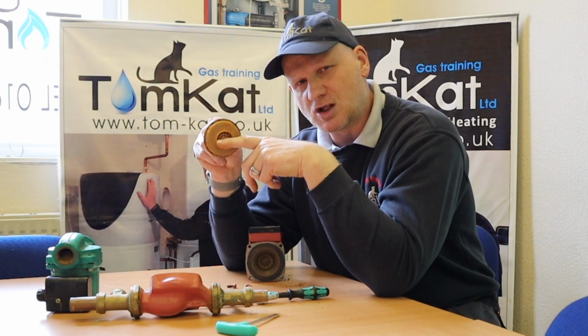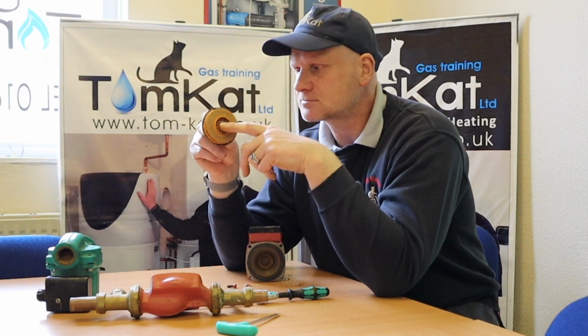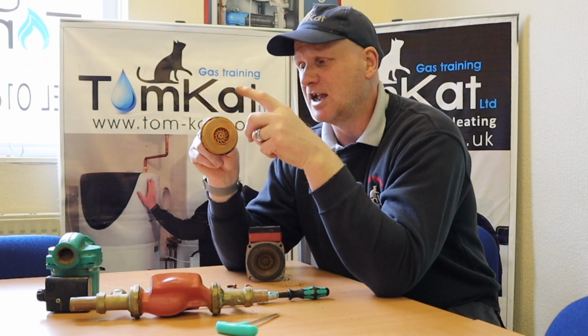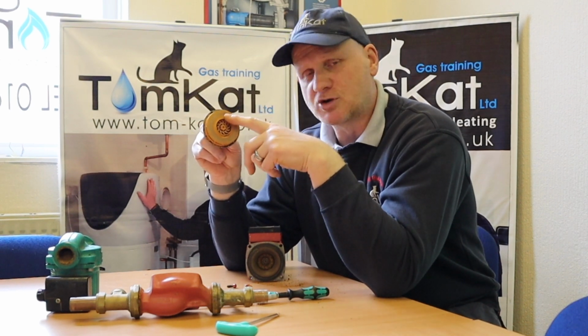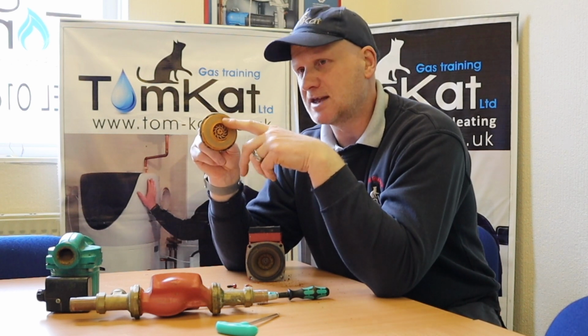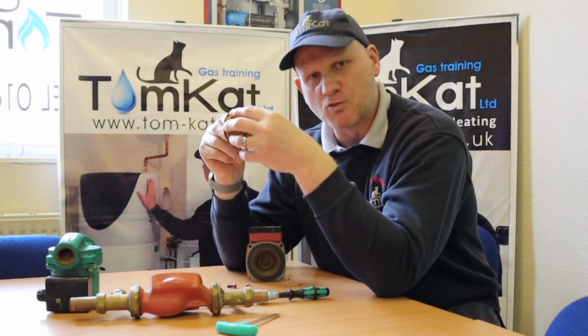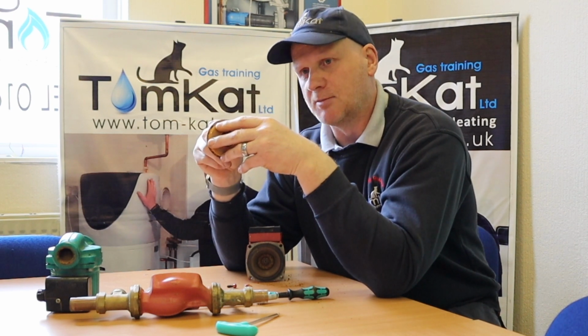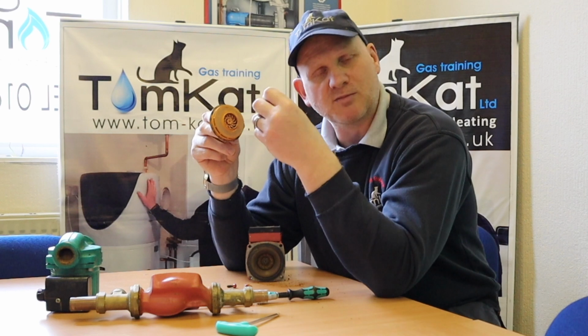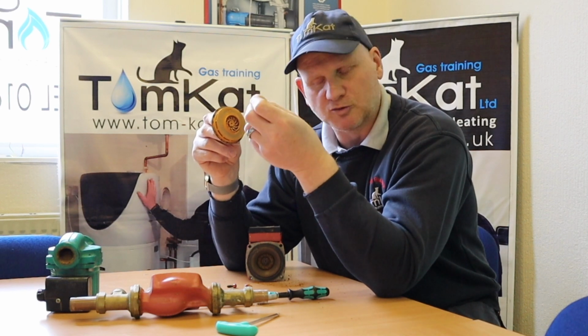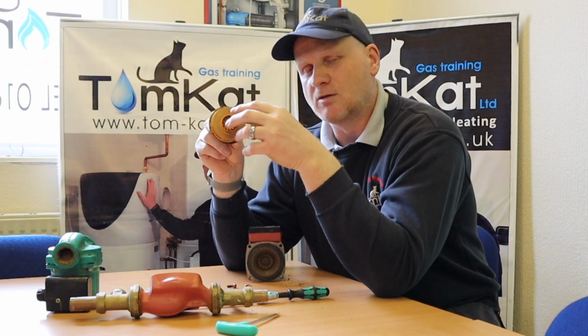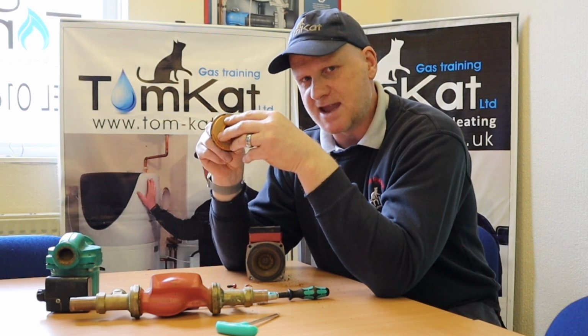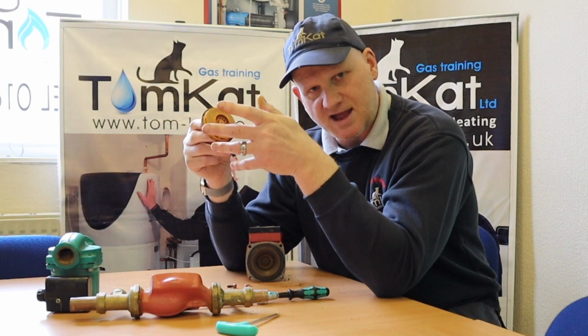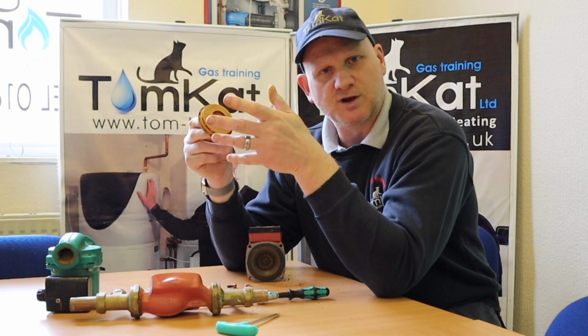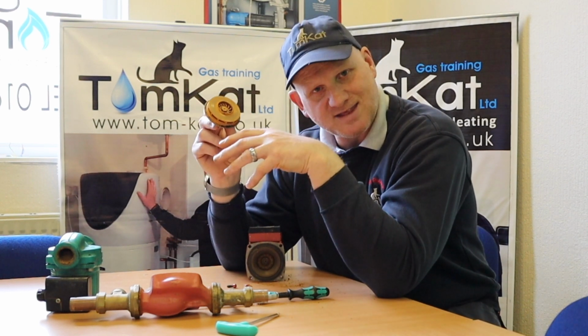Now, what the impeller can also do is what's called cavitate. Cavitation is basically, if the impeller's spinning, it will create air bubbles, and it basically makes the water around the impeller boil and creates these air bubbles. If you've got a noisy pump, you can hear the air bubbles popping. So that's not good for a central heating system. If we're making air through cavitation, then we're creating corrosion. This cavitation as well creates heat.